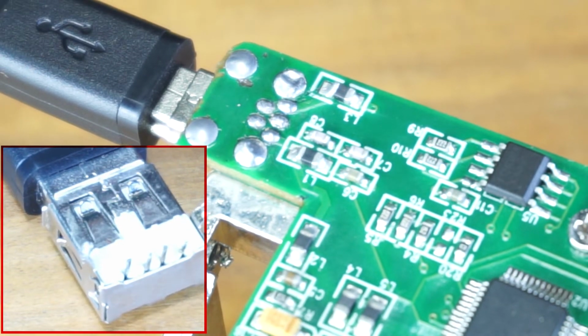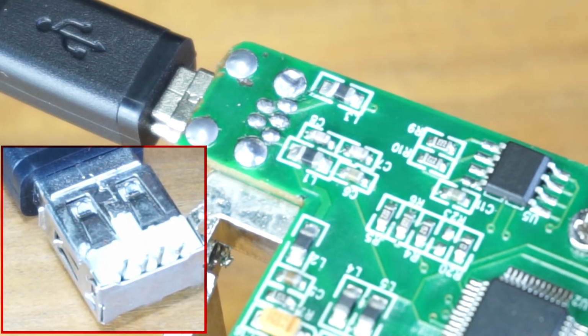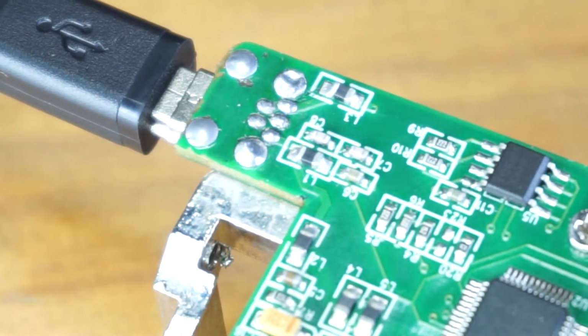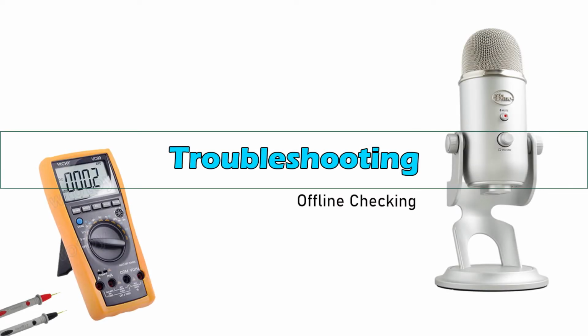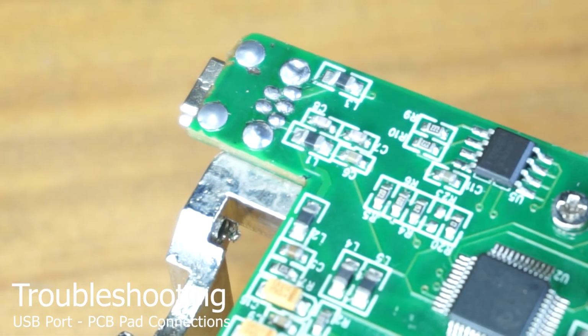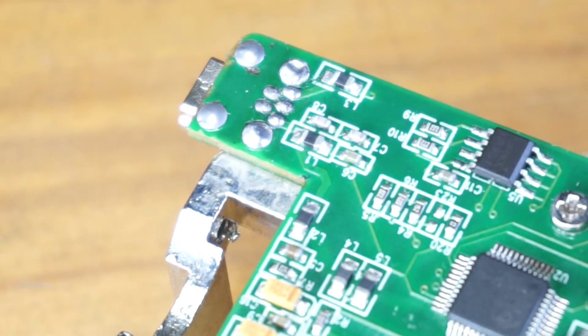As you heard, we have continuity in all these pins, which means the connectivity between the USB cable and the USB port is good. If there was no sound on a pin, it means there is a bad connection between the USB cable and the port. To fix it, you need to replace the USB port. Let's check the connection between the pins of the USB port and the corresponding components that they are connected to at the other end. I'm going to check the connectivity between the USB port and the components of the PCB.